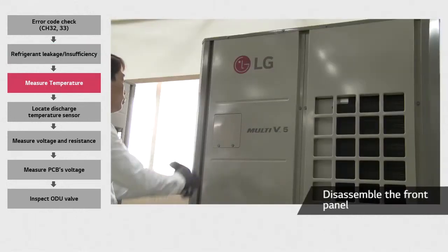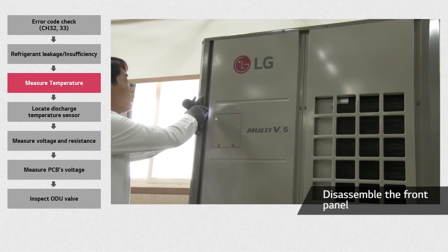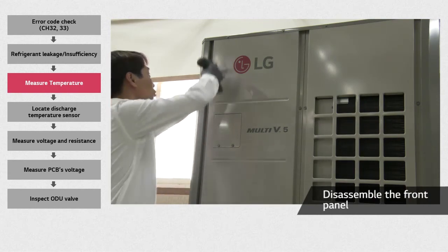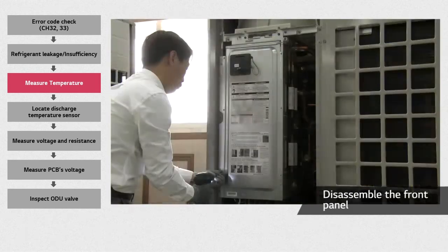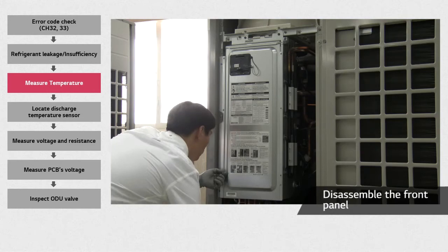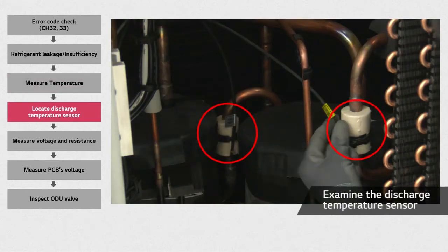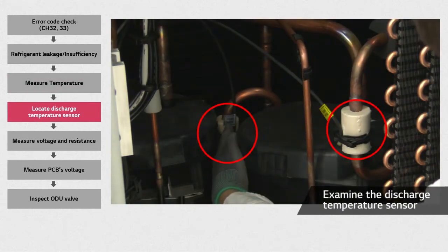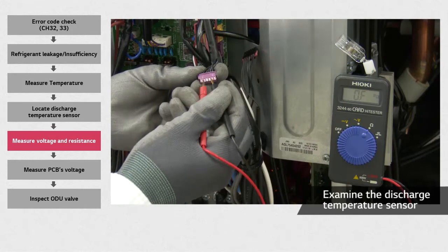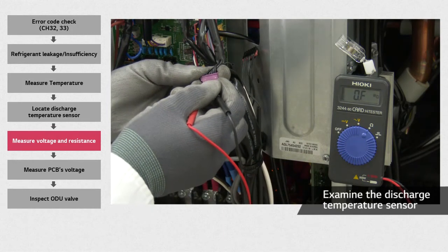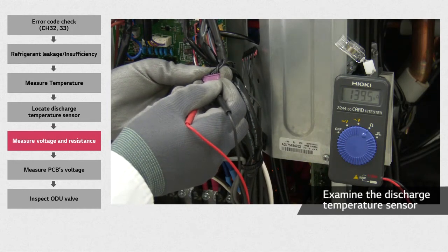If no leakage or damage to the piping is found, you will have to inspect other factors. First, remove the front panel on the outdoor unit and then disassemble the control box. Check that the discharge temperature sensor is in the proper location. Measure the resistance across the two lines of purple and black connectors connected to the external PCB. This error will occur if the value is greater than 5 megaohm or smaller than 2 kiloohm.